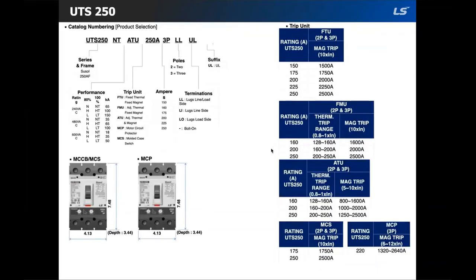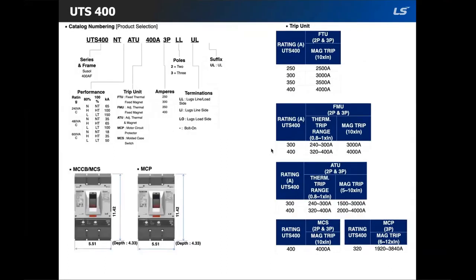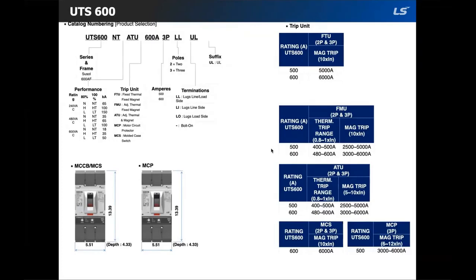And then the next frame size is UTS 250. Just like the 150, it has 6 performance ratings. And it has trip options of FTU, FMU, ATU, molded case switch, and motor circuit protector. And same with the 150, the MCP is only available in 3-pole. Then the next size is the UTS 400, with 6 performance ratings and the same trip units as the 250. So pretty much the same system here. And as for the 600, it's also going to be the same: 6 performance ratings and the same number of trip units.